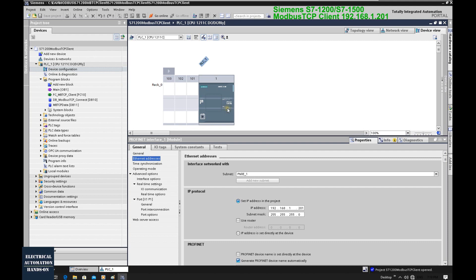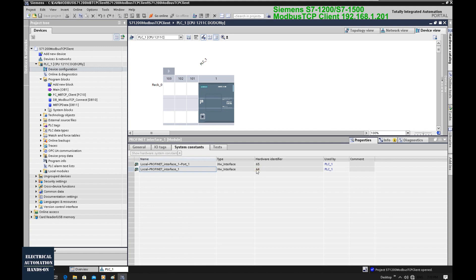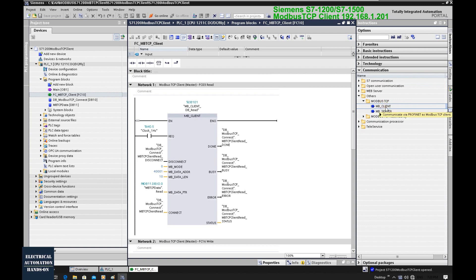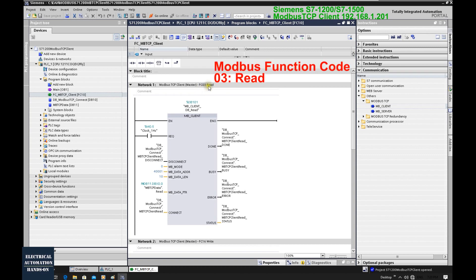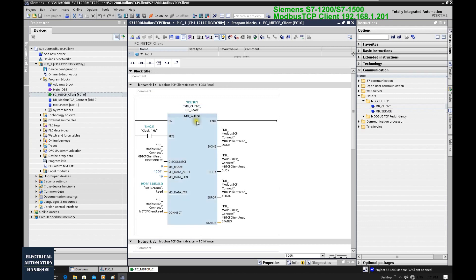Now let's shift to the Siemens TIA Portal side. I'm using the S7-1211C controller with an IP address of 192.168.1.201. As shown in the previous video, this controller will run as a Modbus TCP client. The Ethernet port system constant is 64. To implement the Modbus TCP client, I programmed FC10. To find the Modbus client function block, go to Communication > Others > Modbus TCP, then drag the function block in. In this test, I'm going to test Modbus TCP function 03 — reading from the server to the client — and writing from the client to the server. I implemented two functions with two instance DBs.